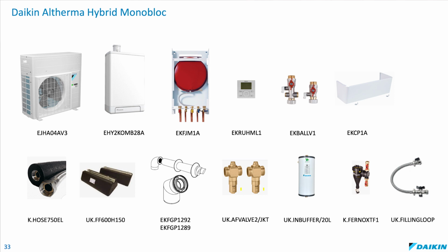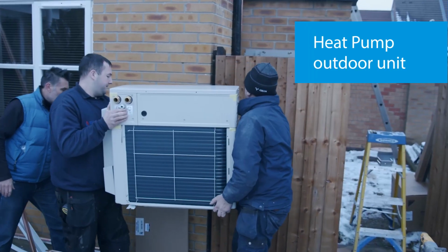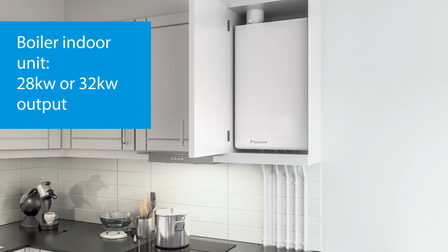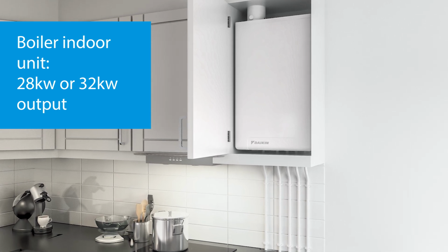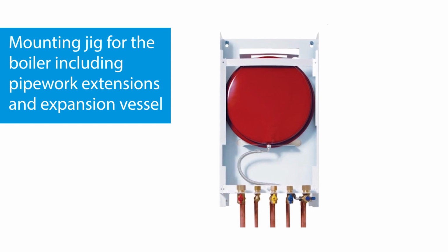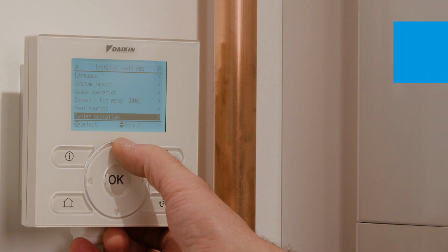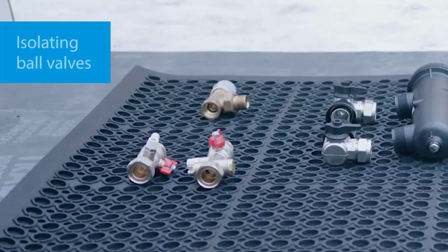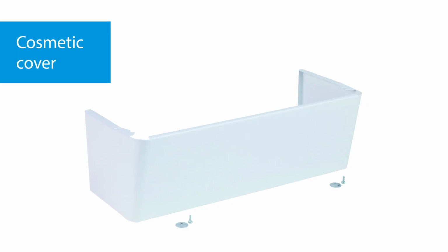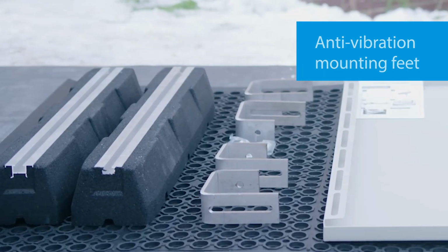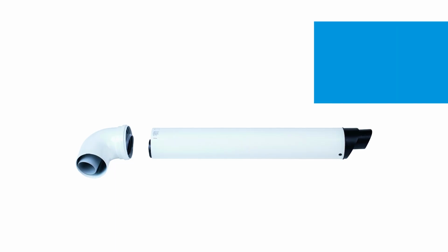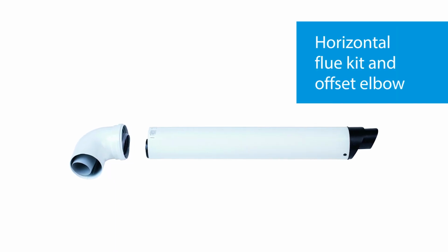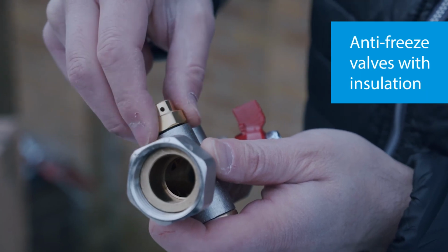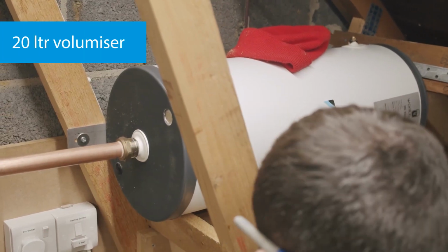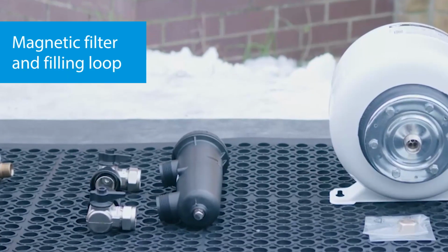The kits include the heat pump outdoor unit, the boiler indoor unit in either 28 kilowatt or 32 kilowatt output, a mounting jig for the boiler which includes pipework connections and an expansion vessel, the hybrid user controller, isolating ball valves for the heat pump, a cosmetic cover for the pipework underneath the boiler, flexible hoses for the heat pump, anti-vibration mounting feet for the heat pump, horizontal flue kit and offset elbow for the boiler, anti-freeze valves with insulation for the outdoor pipework, 20-litre volumiser, magnetic filter, and a filling loop.